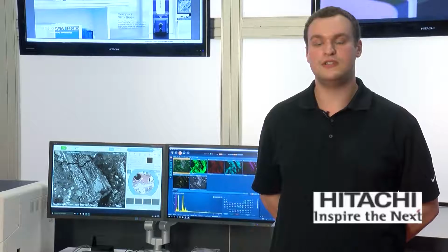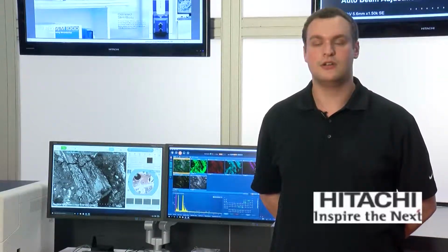Detectors for this scanning electron microscope can be outfitted with the typical Everhart Thornley secondary electron detector, a segmented backscatter electron detector, as well as Hitachi's patented UVD or ultra variable pressure detector utilized in low vacuum environments for secondary electron imaging. Navigation in the FlexSEM 1000 couldn't be easier. There is an optical camera mounted onto the specimen chamber which captures a low magnification macroscopic image of your multiple sample specimen stub for navigation.